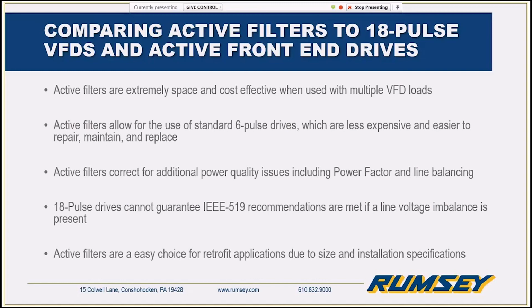And then active filters are really easy for retrofit applications. So if you have a wall space that you're upgrading or you're adding load to, with an active filter, not only is it small, but it can be put hundreds of feet away from where we're correcting. So you can knock a hole and put it in the other room, or you can put it outside in a different type of enclosure. It gives you a lot of flexibility. We have that happen a lot whenever a facility is not aware that they have to meet IEEE 519, and then all of a sudden they need to, and bam, they put us outside to cover for it.